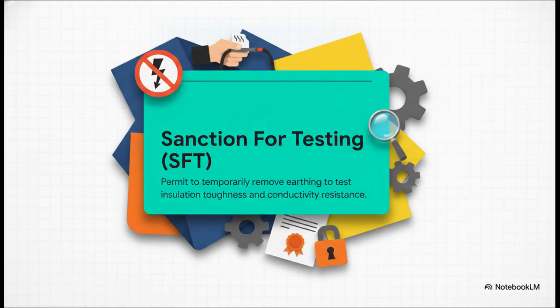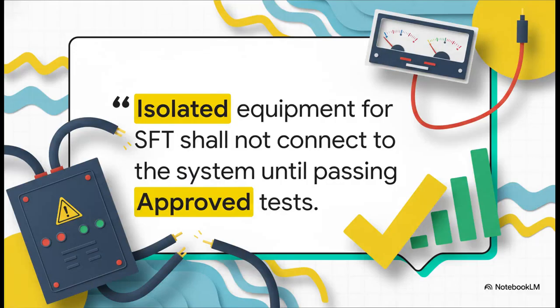It needs direct authorization from the control engineer, and honestly, it puts an immense amount of responsibility squarely on the authorized receiver running the test. I actually want to read this directly from the SEC's safety rules because it's essentially the golden rule of the SFT process. Any equipment that has been isolated and earthed for an SFT shall not be connected to the system until such equipment has passed the approved tests. It is that simple. You never, ever declare a system ready for energization until every single parameter has passed and the control engineer gives you the green light.